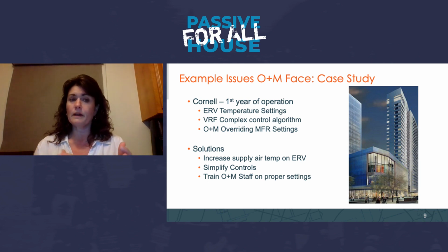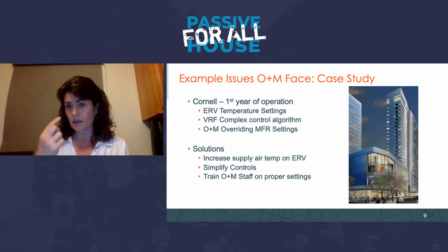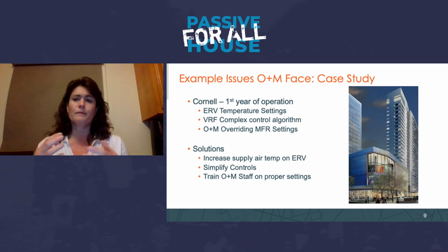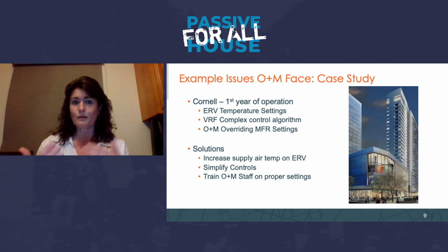The VRF system had a complex control algorithm associated with it. Instead of just switching it from heating to cooling at a certain time of the year, the company set it up so that it had an algorithm that would look at the outdoor temperature and the number of people on a particular condenser loop that were calling for heating or cooling. And it was very, very complex. And what happened was it kept switching from heating to cooling to heating to cooling.